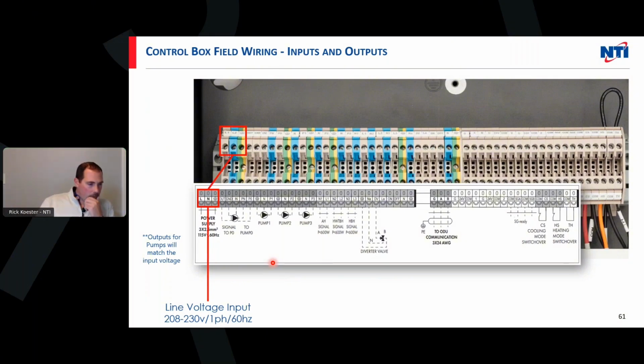All right. So control box being 208, 230, or 115, I have it labeled that way. You can see the 115 is labeled on the actual diagram. So when a contractor looks at the IOM manual, they're going to see that 115 volts. We have 4 separate circulator outputs here. So starting with left, we'll go from left to right here.